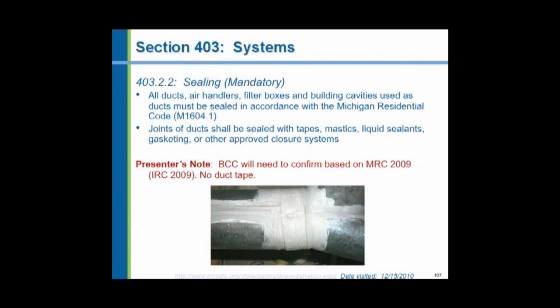There are aluminum foil tapes available. Some are reinforced even with a fiberglass thread. Aluminum foil tape is commonly used on air supply duct board. That's a rigid fiberglass board with an aluminum foil vapor barrier, and all the joints and the seams are sealed with an aluminum foil tape, commonly not reinforced. However, I have seen instances where the aluminum foil tape will not even last a year. Its adhesive will cure and the tape will fall away. So be very careful about what kind of tape that you choose to seal up ductwork.